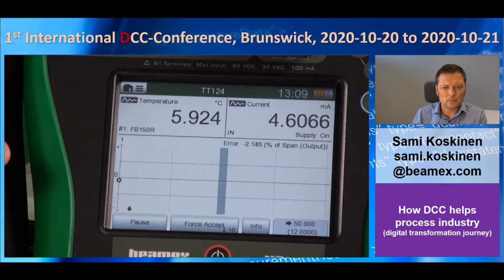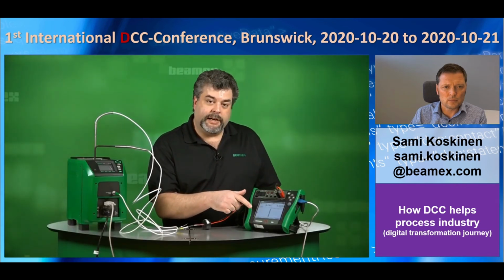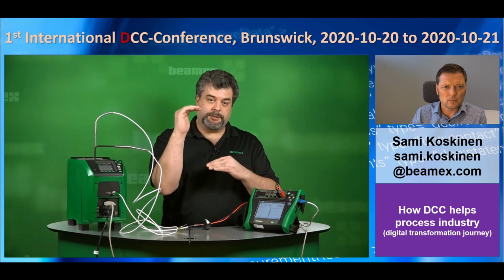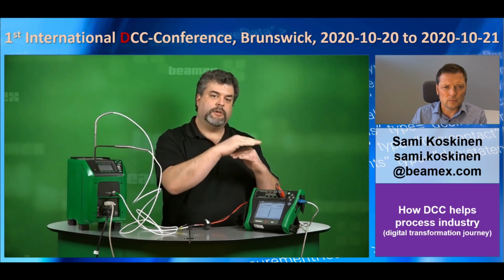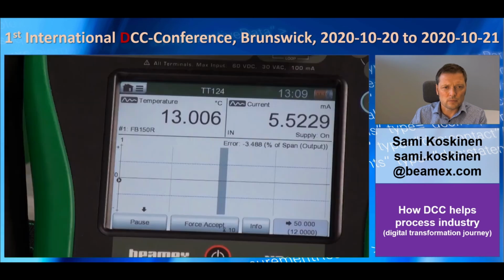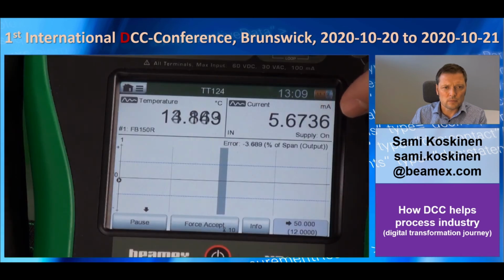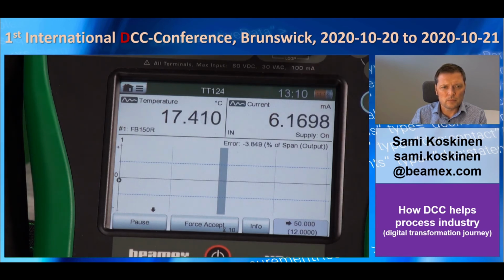The next section down is the graph. So the graph is where are we on this calculation. So the middle line is our 0. If there's no error, our test points will be across that all the way. The blue dotted lines above and below our 0 represent our tolerance. So our test points can be within the blue lines anywhere down the graph and still pass. We're getting a live reading of error, and as we're heating up there's a little bit of a delay from our temperature probe, and that's why we have a settling delay at the end anyway. At the bottom we have a pause button, so we could pause our calibration if we needed to for some reason. So at this point now, we just wait for it to hit 50 degrees C and grab our second test point.